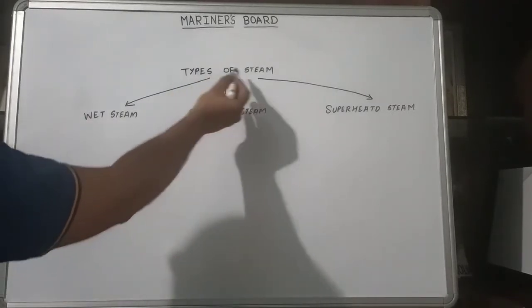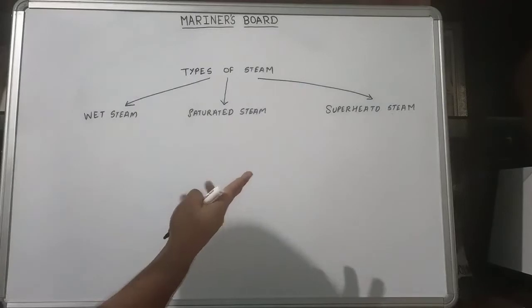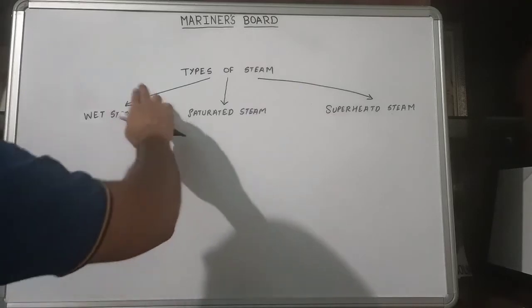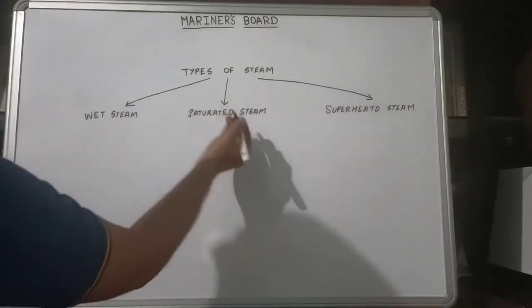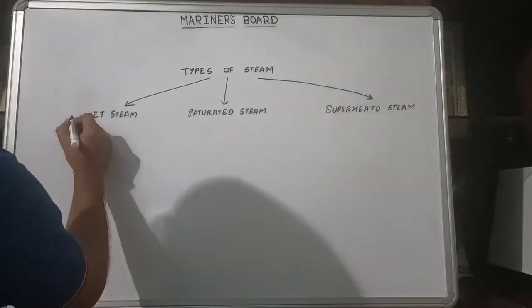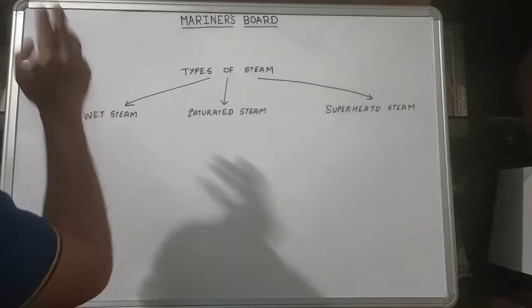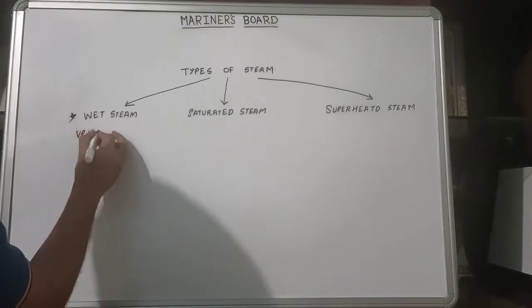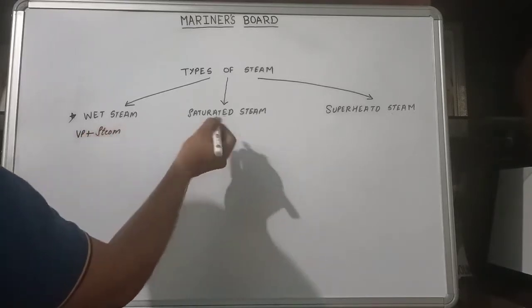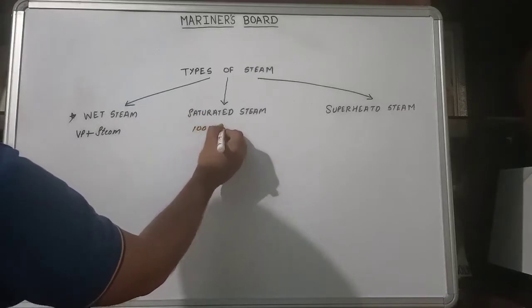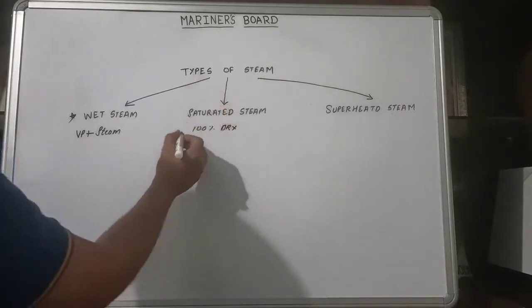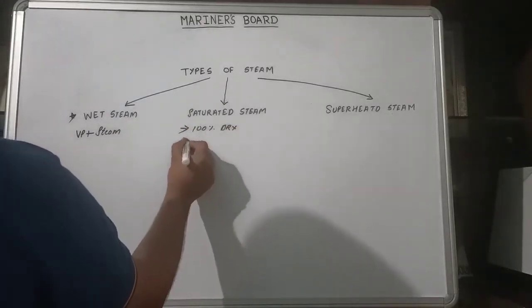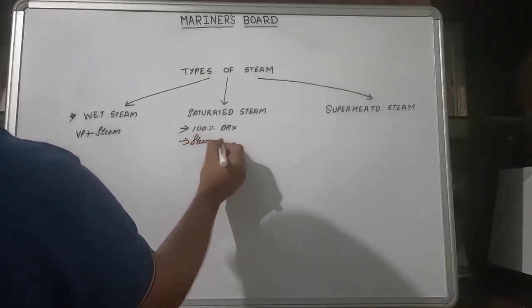Before understanding the basics of boilers, let's look at the basics of steam. There are basically three types of steam: wet steam, saturated steam, and superheated steam. Wet steam has water vapors along with the steam. Saturated steam is 100% dry and does not contain any water vapor. The amount of vapors present in steam can be expressed by the steam dryness fraction. If steam contains 10% water by mass, it is said to be 90% dry, or has a dryness fraction of 0.9.